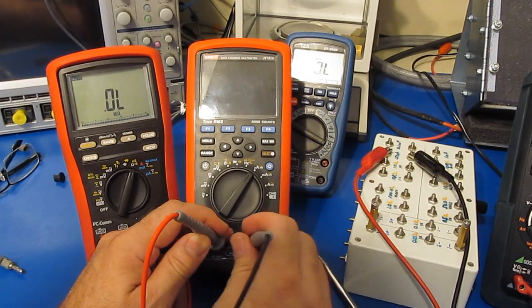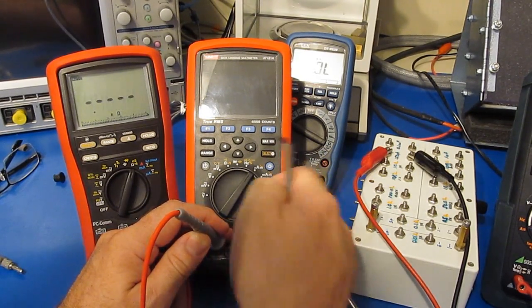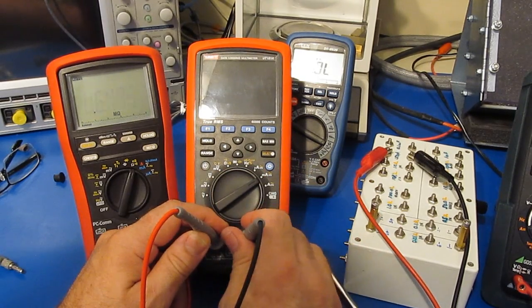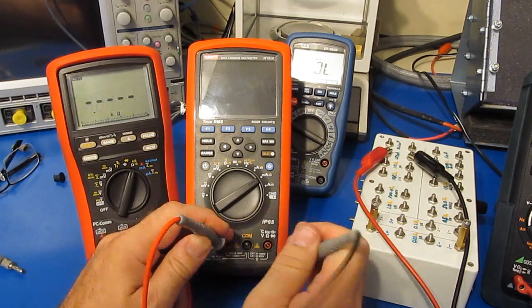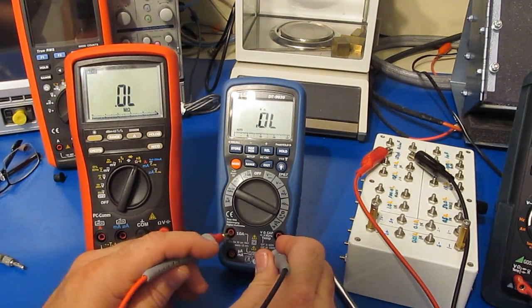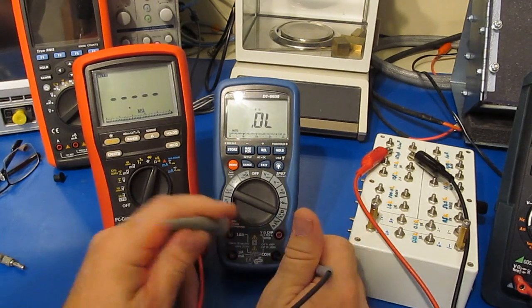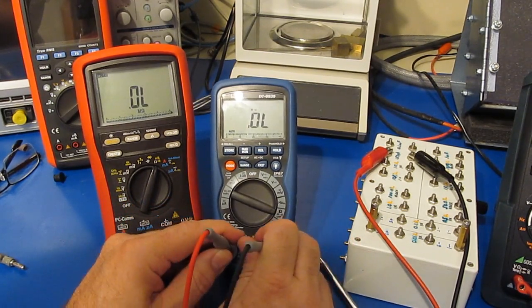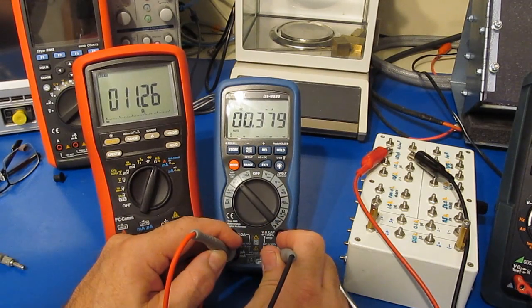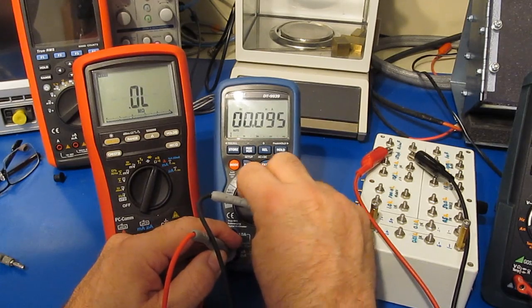So 50 ohms in that range, and I expect this is like an ohm. Yeah, so let's just see if I go between the common - there's our shunt. And let's try it with the milliamp microamp - yep. And again you can see it has to be switched to the milliamp or the microamp range. And in this case this 4 to 20 input should also engage that.